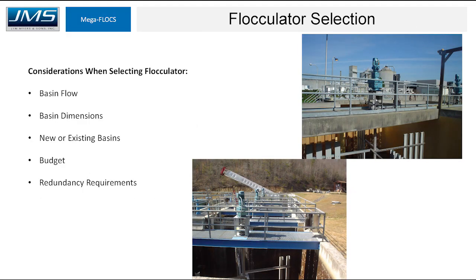Some considerations when selecting between flocculator technologies are usually basin flow — some technologies are not cost-effective for large flows. The basin dimensions also matter, as flocculators must be arranged to eliminate dead zones and prevent short-circuiting. For new or existing basins, they may or may not be able to support vertical-type mixers; you may have to add steel or concrete bridges.